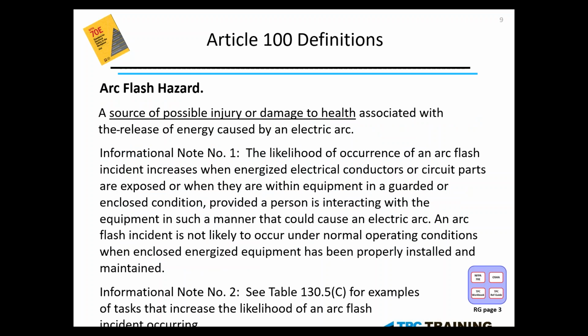I'm going to go through a few definitions here and then help identify any particulars as we go. The first one is arc flash hazard. Arc flash hazard is identified as a source of possible injury or damage to health associated with the release of energy caused by an electric arc. So basically, whenever we get our current flowing outside of its normal path, there's the potential, or as it says here in the first informational note, the likelihood of an occurrence of an arc flash. When this occurs and it cannot be put into a safe working condition or de-energized, then we must be protected against that hazard. The word shall will come into play quite a bit here. The employer shall protect us if it cannot be eliminated.